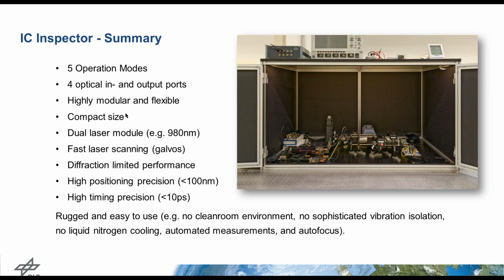Our system is quite compact and highly modular, so we can adapt easily to new analysis methods and also different ICs. This is the main feature of our system. Here you can see the area where we put the device under test. This region is the near-infrared microscope. The SPAD, which you can't see, is connected via a fiber here.